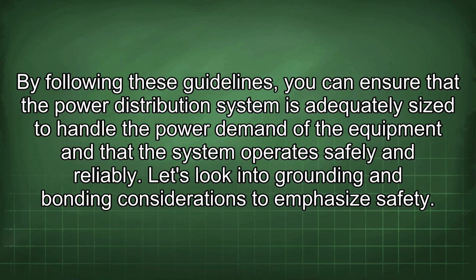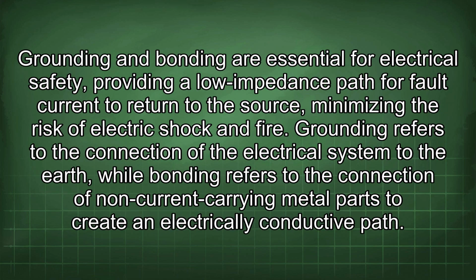Let's look into grounding and bonding considerations to emphasize safety. Grounding and bonding are essential for electrical safety, providing a low impedance path for fault current to return to the source, minimizing the risk of electric shock and fire. Grounding refers to the connection of the electrical system to the earth, while bonding refers to the connection of non-current carrying metal parts to create an electrically conductive path.